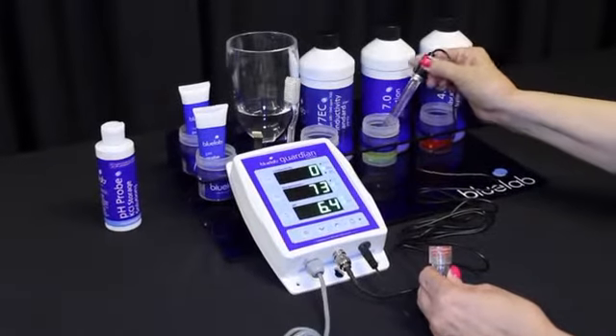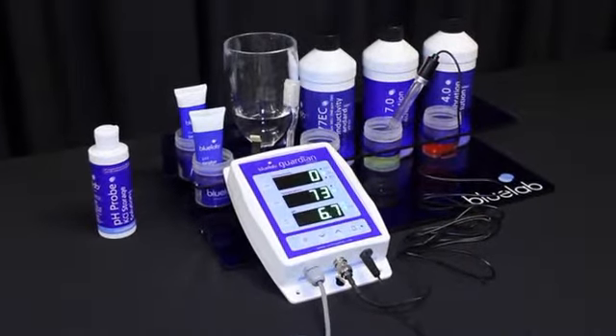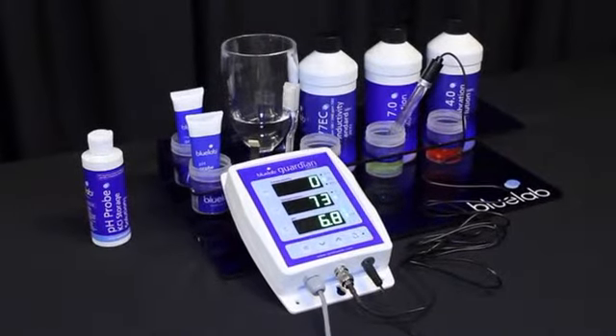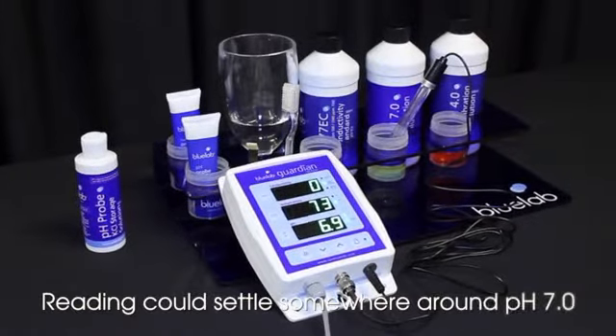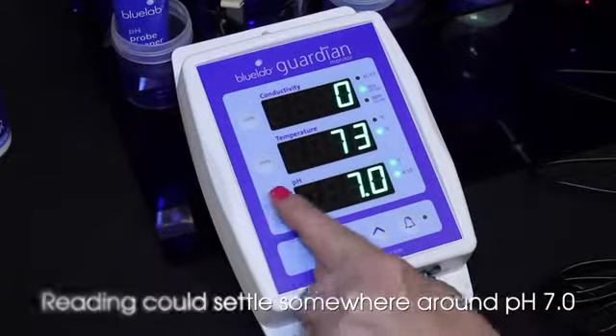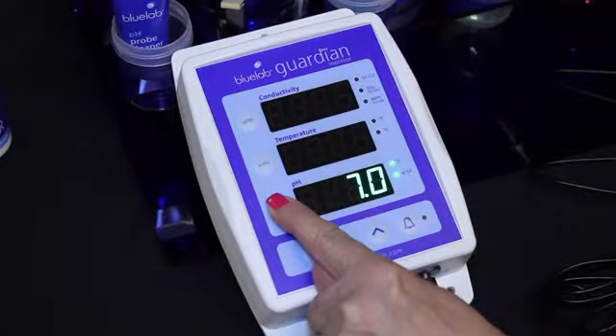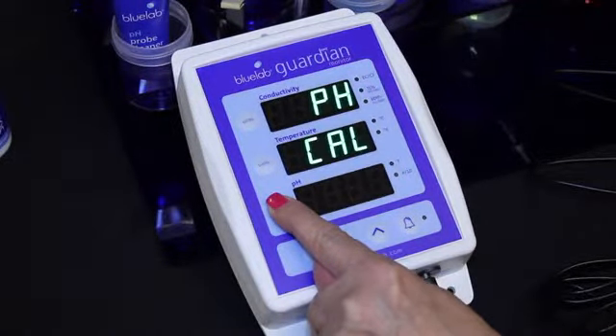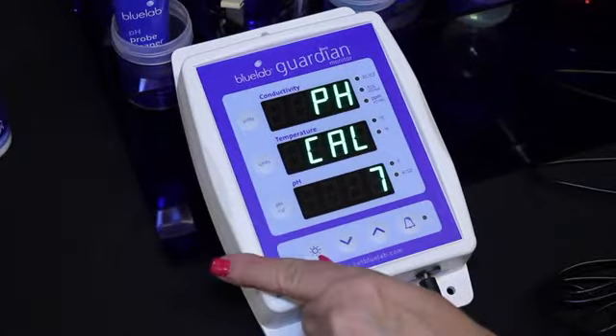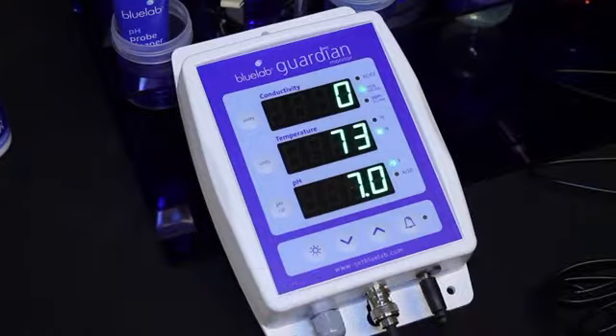With the Guardian plugged into a power source, place the probe in pH 7.0 solution. Be sure to wait until the reading has stopped moving. Press and hold the pH cal button until the display shows pH and cal on the top 2 displays. Release the button. 7 will flash on the pH display. Then the pH 7.0 indicator light will glow.